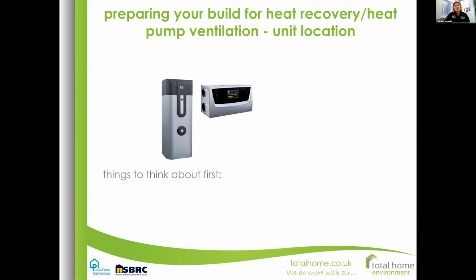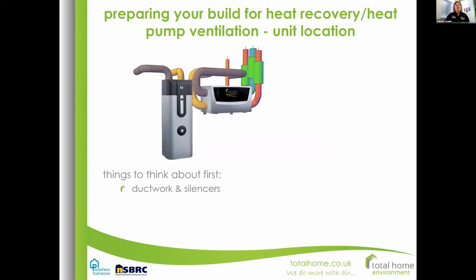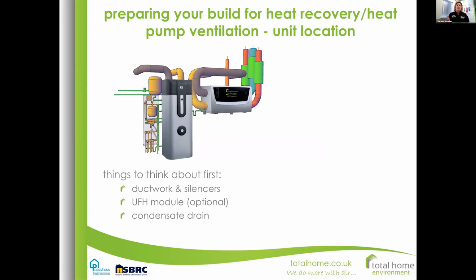So thinking about where the units are going to be placed, it's not just the units that you have to think about. Don't just look at the specification sheet and think that's it. You are going to have bends off the units, you're going to have silencers. If you're going to have any connections to underfloor heating from your water heat pump, then there needs to be space for that. The ventilation unit is going to be creating condensation. It's collecting moisture in the air, so that needs to be removed from the unit. So a plumber will need to get involved in plumbing that up to the house plumbing system. Filter maintenance, are you going to be able to physically pull out the filters in front of the unit? Because you need to check those every quarter or every 6 months. Insulation, there will be insulation around the ductwork as well. Is the location going to be in a room, a place where it's still within the thermal envelope?